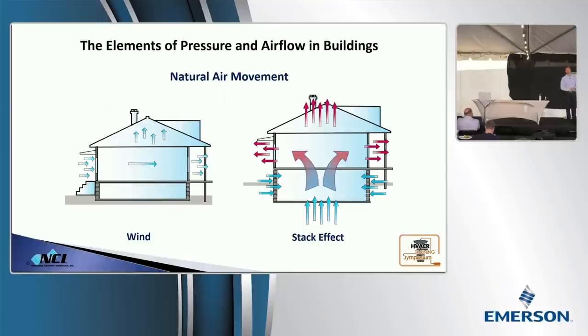Air changes directions in the summertime. This is why we don't see it, why it's more prevalent. Those arrows, they flip in the summer. You have hot, warm air coming in through the upper spots. Cool air leaves down low. Those of you that are in cooling-dominated climates that have multi-story homes, if you can hang meat on the first floor, but it feels and smells like the attic on the second floor, you're fighting a leaking building. It's bringing probably 10 tons of load in through the attic to a system that may only be designed to handle 3 or 4 tons. You can't counteract that with HVAC. This type of an effect affects combustion air.